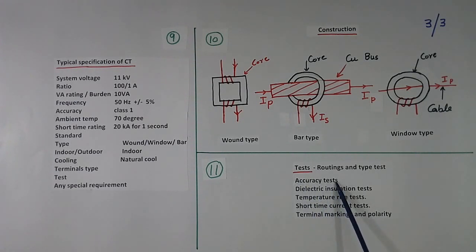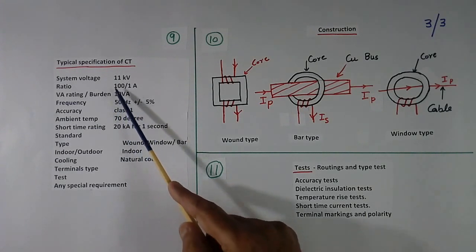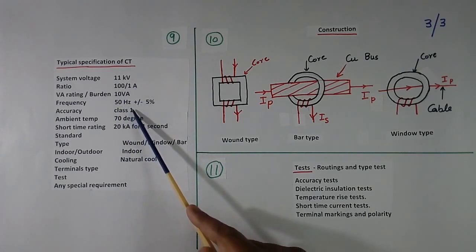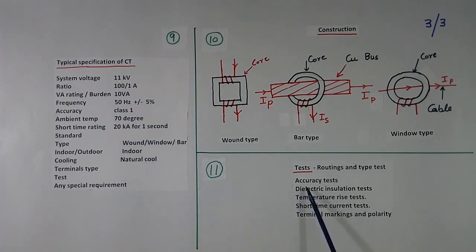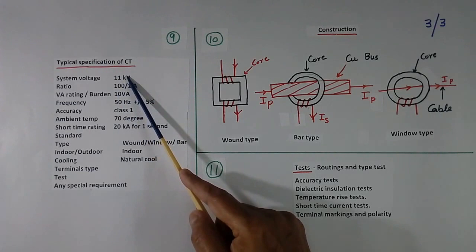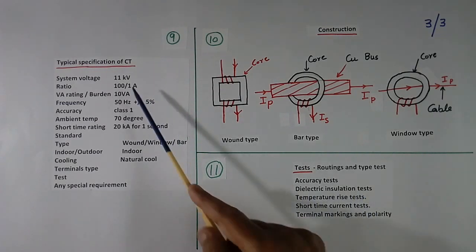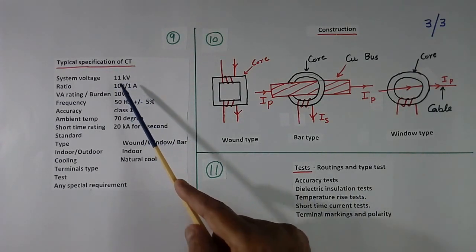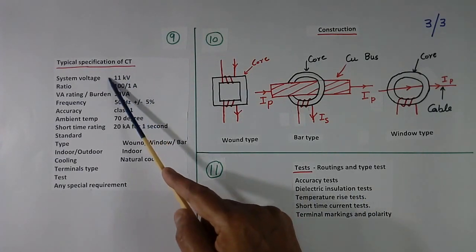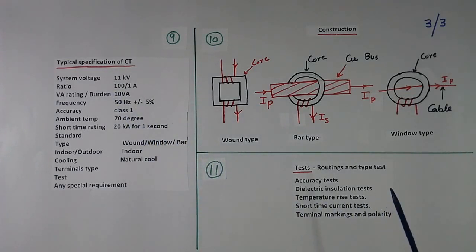First accuracy test. We have written here accuracy class 1 and ratio this. So we check whether it is meeting 1% tolerance or not. Then we check insulation test. This is 11 kV. So we have to check whether 11 kV it can take or not. Generally voltage apply here will be much more than this. For example, if it is 230 V, voltage apply will be 2.5 kV for few minutes.